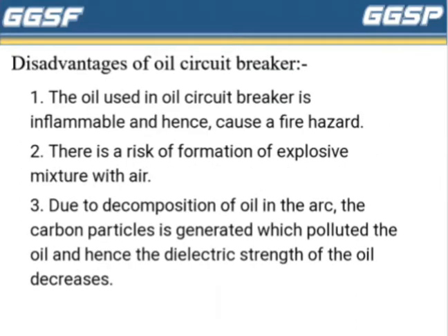Disadvantages of oil circuit breakers are as follows. First, the oil used in the oil circuit breaker is inflammable and hence it can cause a fire hazard. Second, there is a risk of formation of an explosive mixture with air. And third, due to the decomposition of oil in the arc, carbon particles are generated which pollute the oil, and hence the dielectric strength of the oil decreases.